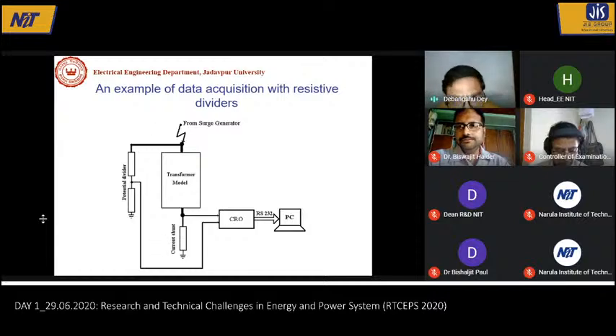This is one typical transformer impulse data acquisition setup network. This is the impulse from the surge generator that can be given to the actual transformer. In our lab, the data I'll be showing is on a real life model of the transformer - that is why it is written as transformer model. In a real case, that model will be replaced with a real life transformer.